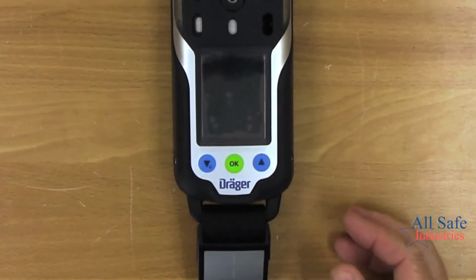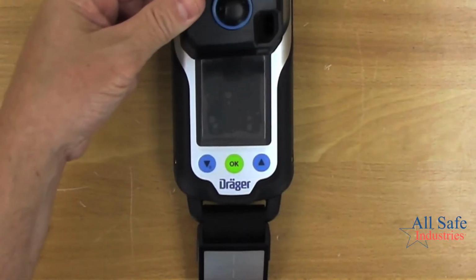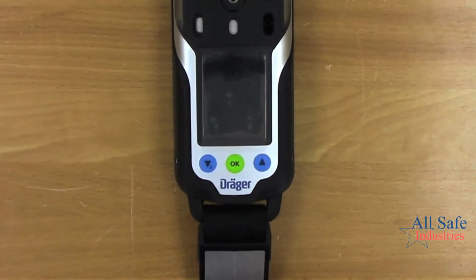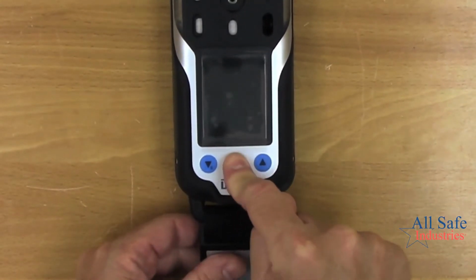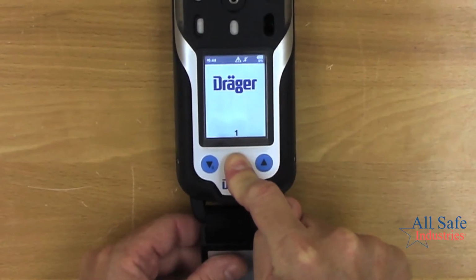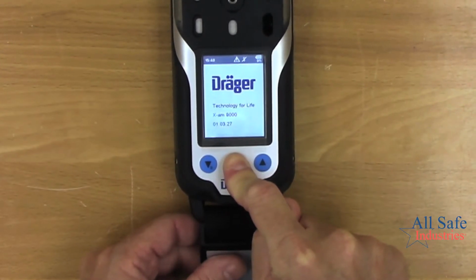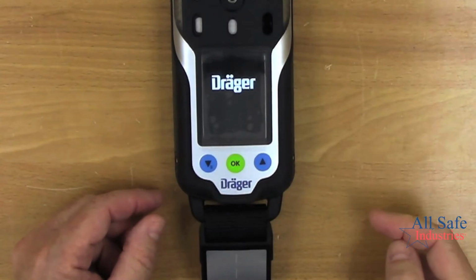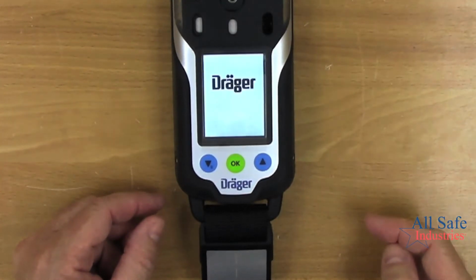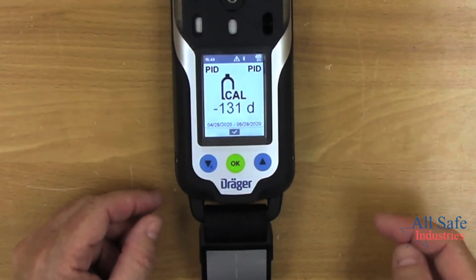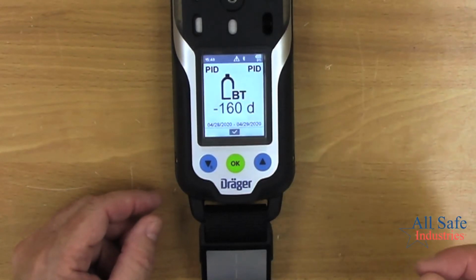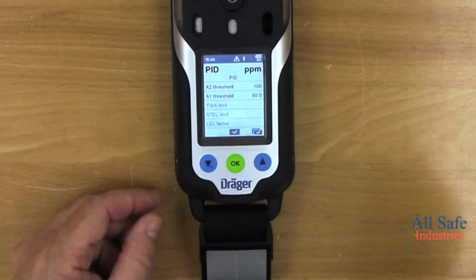The same pump cap could be applied to this instrument to make it a pumped unit. Let's go ahead and turn on this unit and show you a couple of extra features with the X-am 8000. This unit has 5 sensor positions, and with some dual purpose sensors, that gives us the ability to read between 1 and 7 gas displays on the screen all at one time.